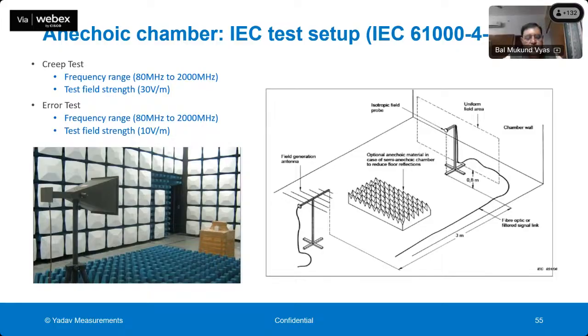So you can see the meter is placed at a particular place, and you can see a horn antenna. This horn antenna is generating the radio frequency field, and this field is imparted on the meter from 80 megahertz to 2000 megahertz and so on. If we test up to 6000 megahertz, 6 gigahertz, the frequency is increased with a 1% step size, and for the creep test, the field can be 30 volts per meter. Means when a 30 volts per meter field at different frequencies is there, the meter should not start recording energy automatically when there is no load. And another kind of test, again the same kind of field, which is 80 megahertz to 2000 megahertz.